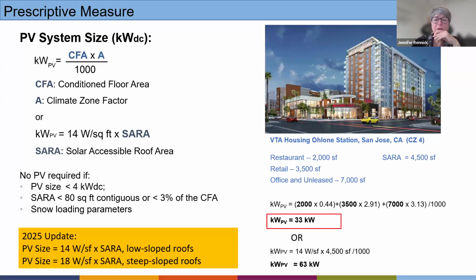And one of the things under the current code cycle is that you could calculate the size or the capacity in kilowatts DC for your photovoltaic system based on the conditioned floor area and climate zone factor based on occupancy and our climate zone. Or you could look at how much roof area you have available, solar accessible roof area, and multiply that times 14 watts per square foot. And then you choose one or the other based on which one was less.